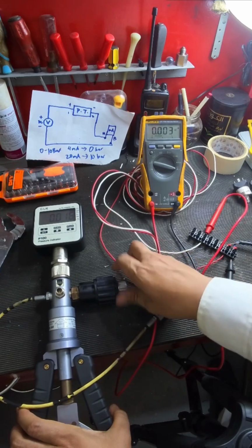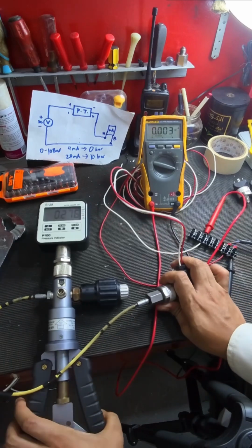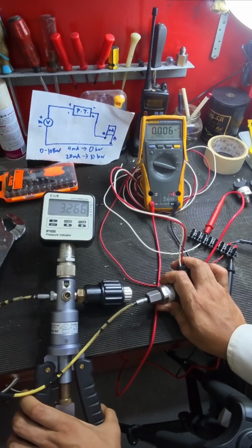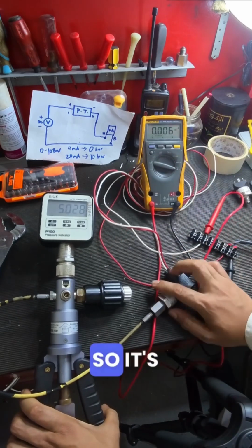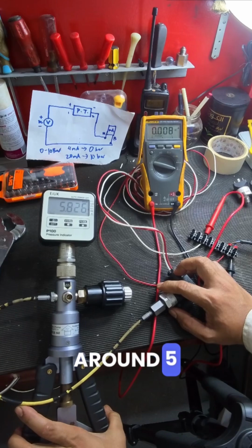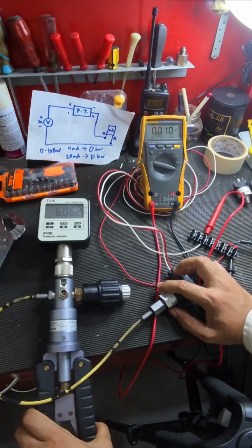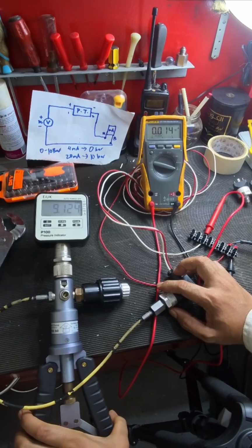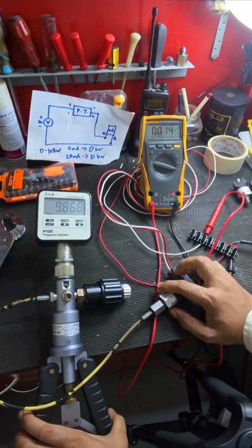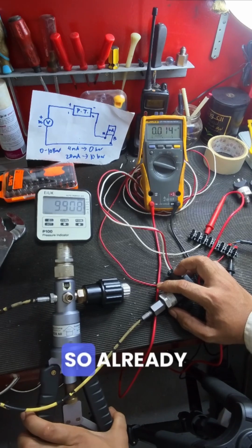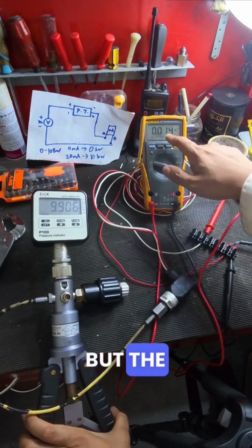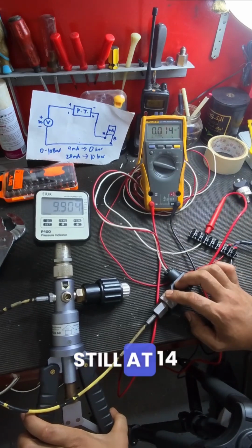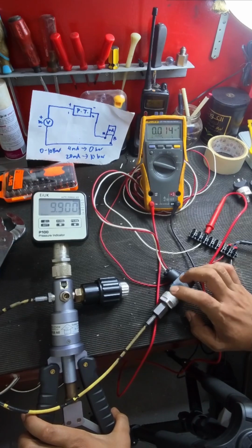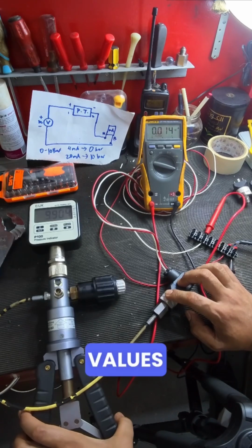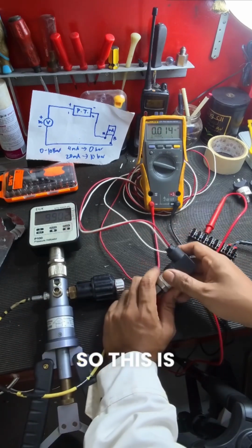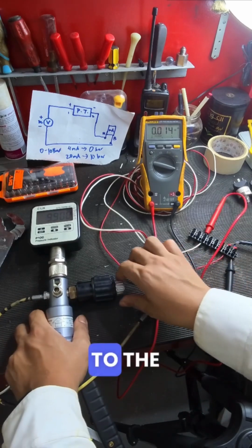So let's try to pressurize the sensor. As you can see, at 4 bars it gives 6 milliamps, so it's already out of range. At 5 bars it should be more than 10 milliamps already. At the maximum value, the current output is still at 14 milliamps. So this sensor is giving incorrect output values. This is not acceptable. This will give a malfunction to the system.